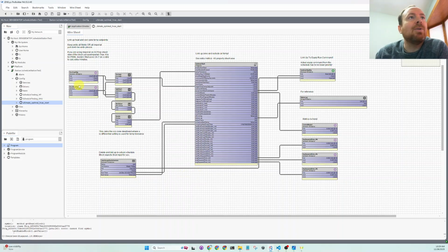We're also incorporating, in building automation, an occupied cooling set point and an effective occupied heat set point. This is typically a zone set point with deadbands factored in. When I deploy this block on the live building automation, I'll copy it into a wire sheet and link these to the actual points.